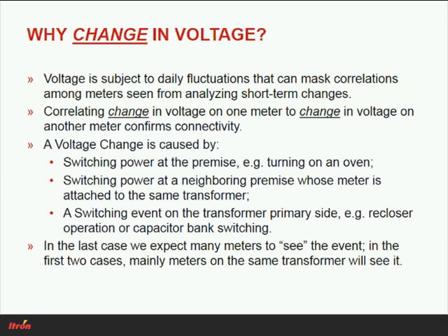So what we found is that the voltage changes correlate quite well for meters that are on the same transformer, not very surprisingly. And they don't correlate well for meters that are on different transformers, especially if the transformers are on different feeders or on different sections.